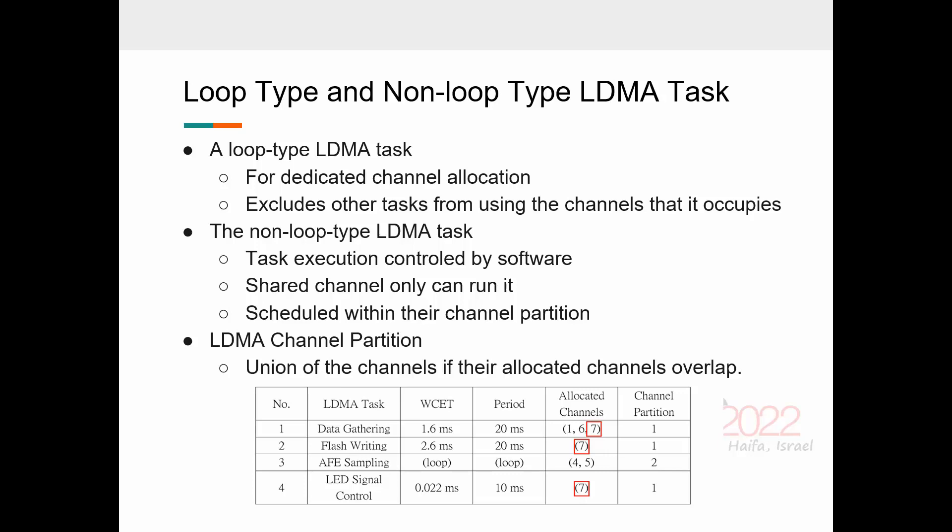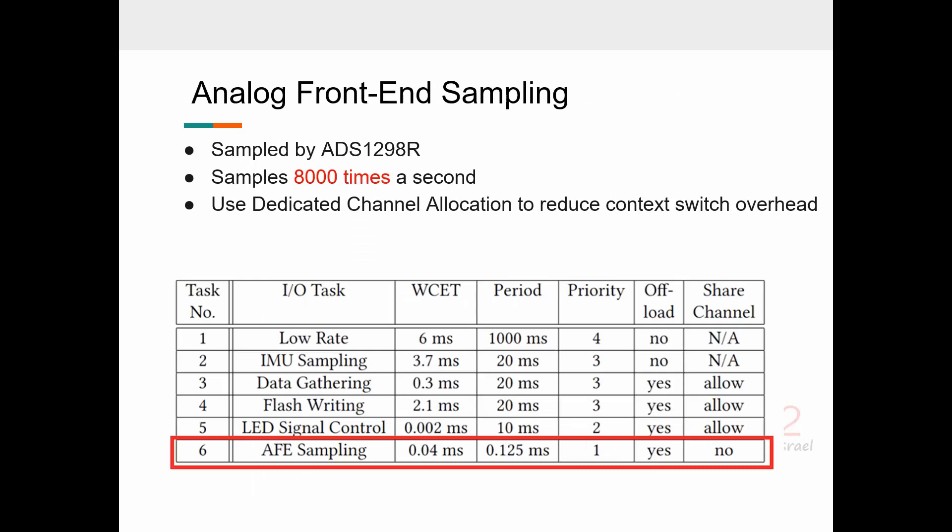After discussing the loop type and non-loop type LDMA task, the question now is, which tasks should be allocated dedicated, and which should be shared LDMA channels? The AFE sampling device is the ADS1298R by Texas Instruments, which contains the analog front end and eight simultaneous 24-bit differential pair analog to digital converters. The AFE sampling task is the most demanding, as it is invoked 8000 times a second, and is a prime candidate for offloading onto LDMA. Because of the high sampling rate, we offload it by the dedicated allocation to reduce the context switch overhead.